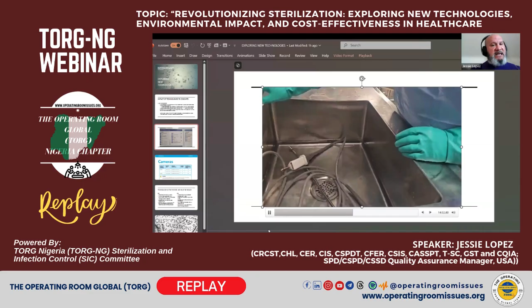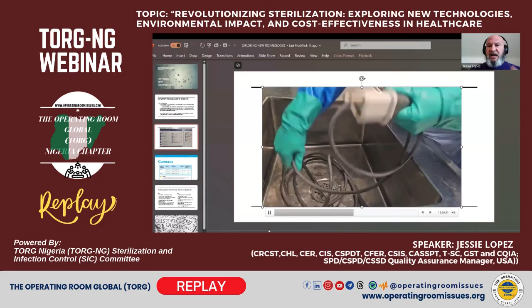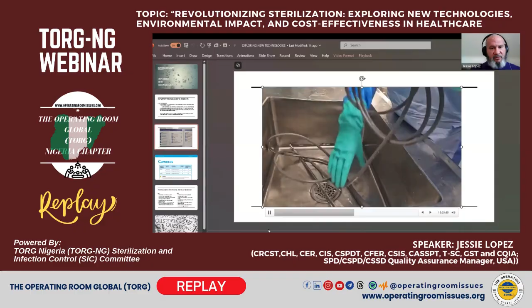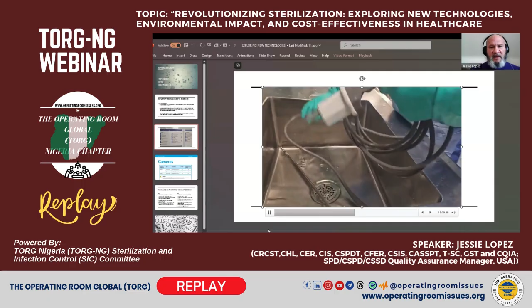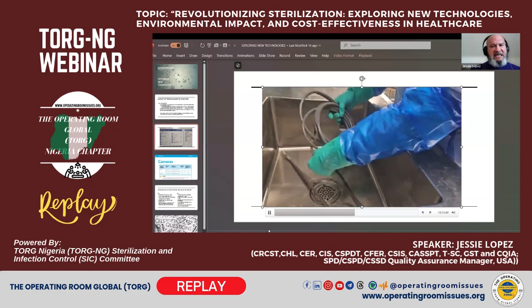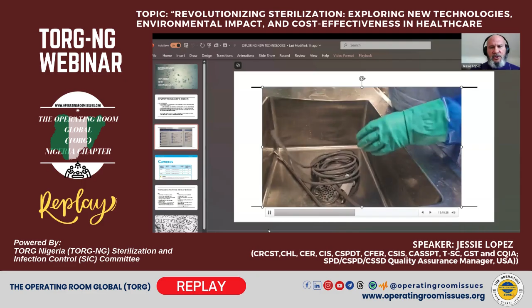The detergents that we use in the manual cleaning portion of this device are typically not compatible with the detergents of the automated cleaning process, because those detergents are non-foaming and are typically easier to rinse off than those of the manual cleaning process. Now you want to coil your cord up in a fashion that, when we place it into the ultrasonic, it is neatly placed in there.